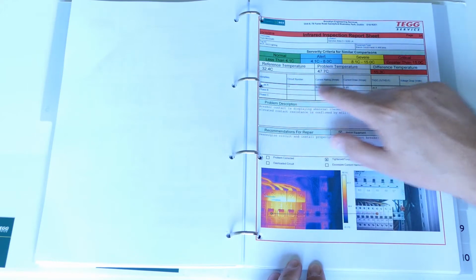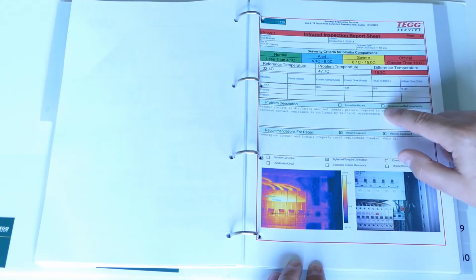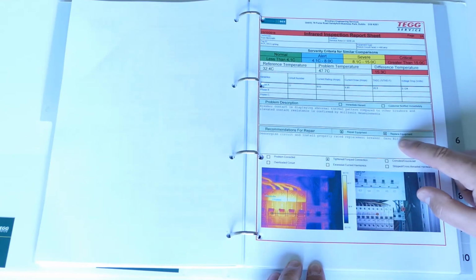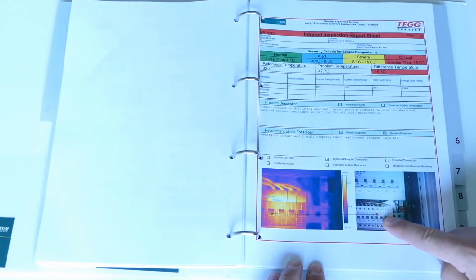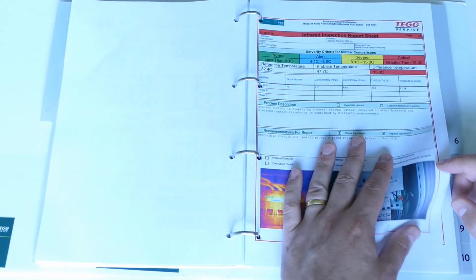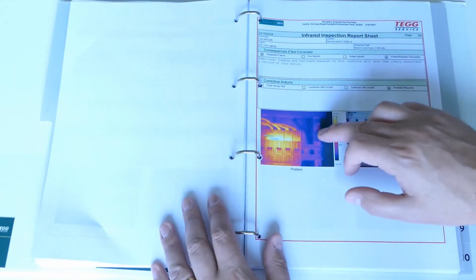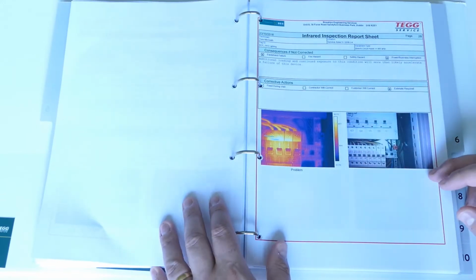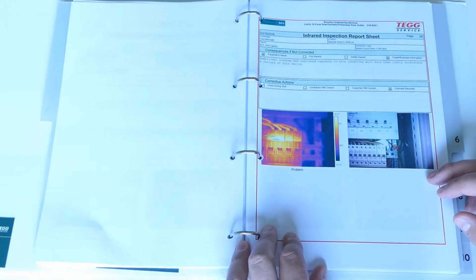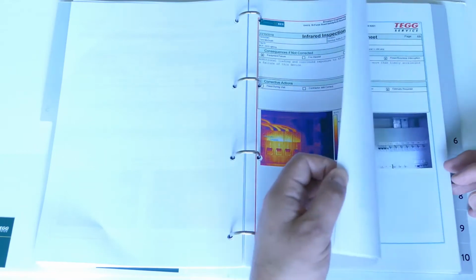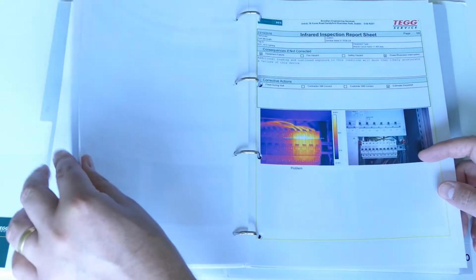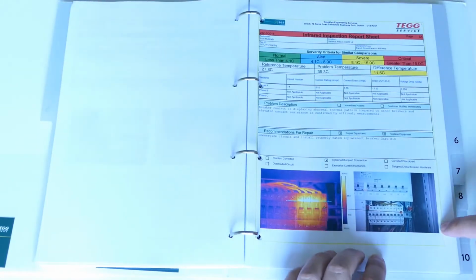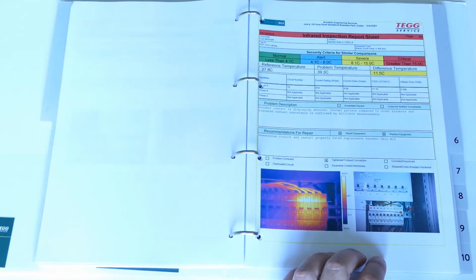We show the loading on the board at the time of test, the problem, the description of the problem, recommendations for repair, and also pinpoint the issue in the image. If the problem has been rectified on site, there'll be a before and after image to indicate that the temperature has dissipated and the problem was rectified. So as this section continues, you'll move into yellow issues, which would indicate that it is a severe, and then further on will be the alerts, which would be again less significant.